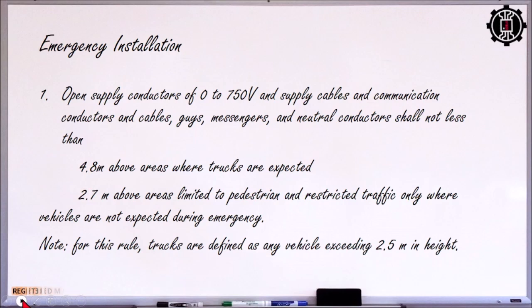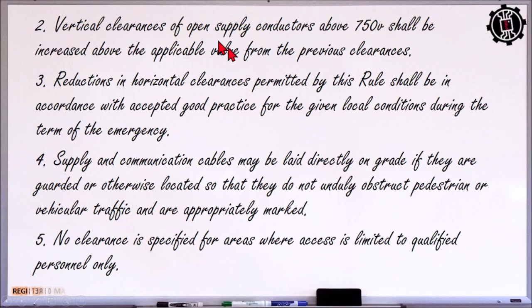Okay. So vertical clearances of open supply conductors above 750 shall be increased above the applicable value from the previous clearances. So if your voltage is above 750, so dapat mataas siya ng konti, no? Siguro depending on the practice, no? But it should not be below the 4.8 meters para sa truck na sa mga daanan na may dadaan na truck or 2.7 meters for light pedestrian. So reductions in horizontal clearances permitted by this rule shall be in accordance with accepted good practice for the given local conditions during the term of emergency.